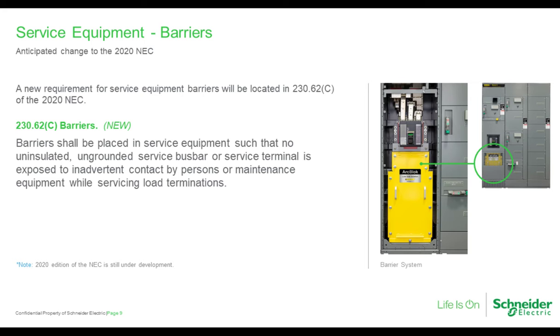However, while a barrier may be effective at protecting against shock hazards, unless it's been evaluated for arc flash protection, it should not be considered to provide protection during an arcing event. And the solution you're going to hear about in a few minutes will satisfy this new barrier requirement, plus it will address the line side arc flash hazard as well.